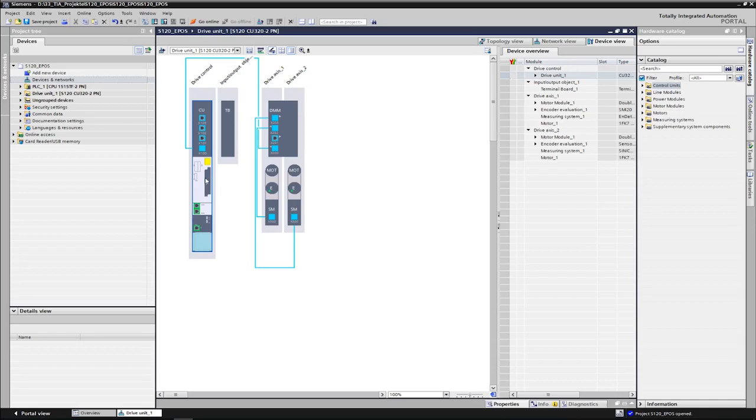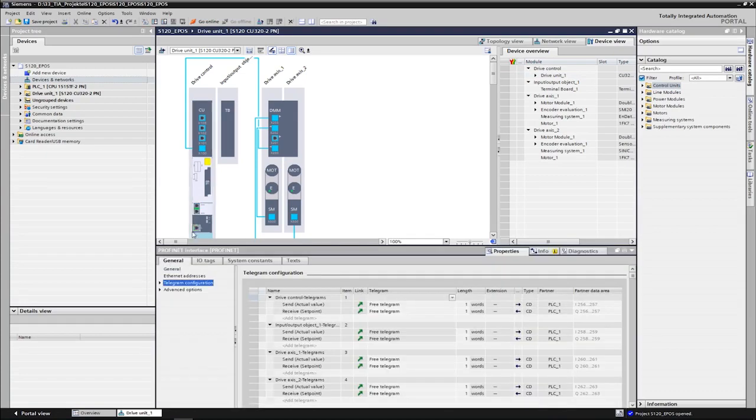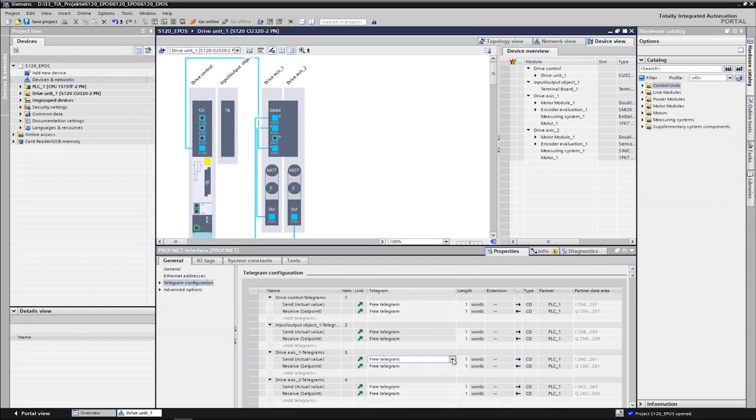The telegram configuration can be found in the device configuration of the drive unit. Double-click on the PROFINET interface of the CU to open its properties. All drive objects are listed on the telegram configuration. Only the possible telegrams are offered under telegram after the function module basic positioner is active on the first axis.